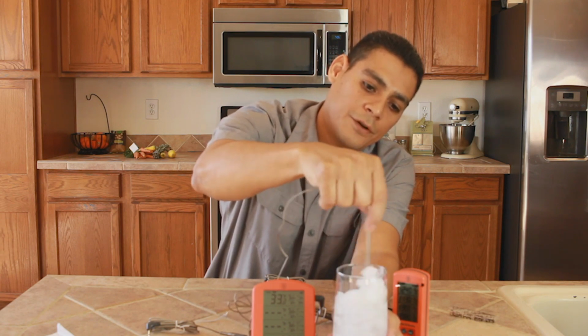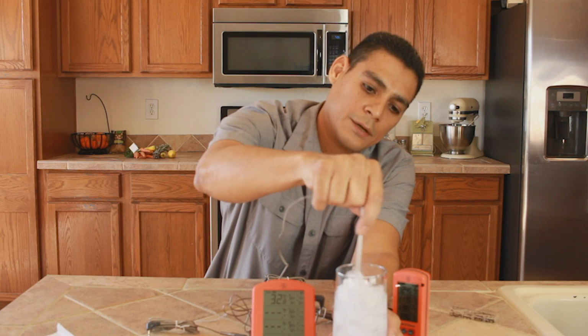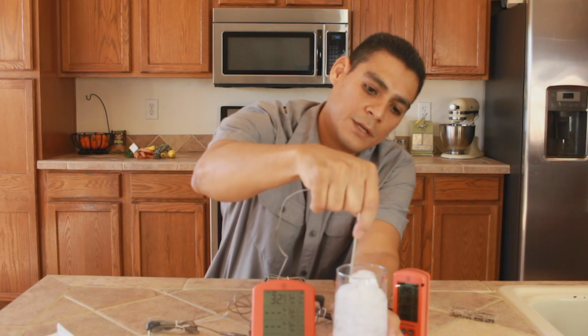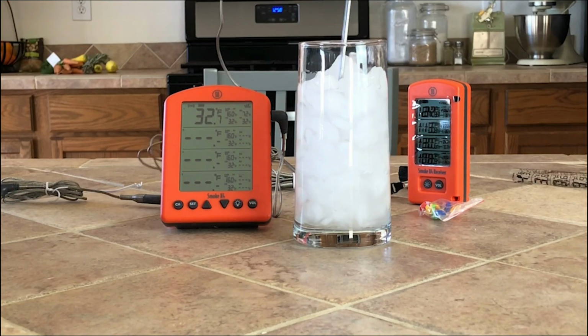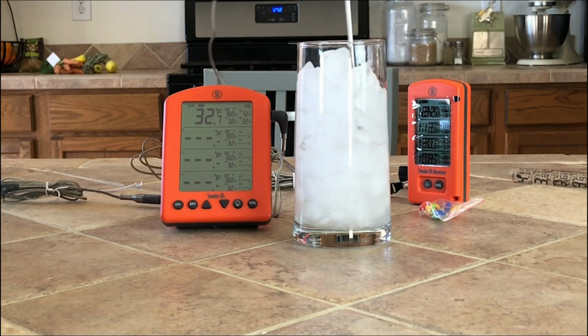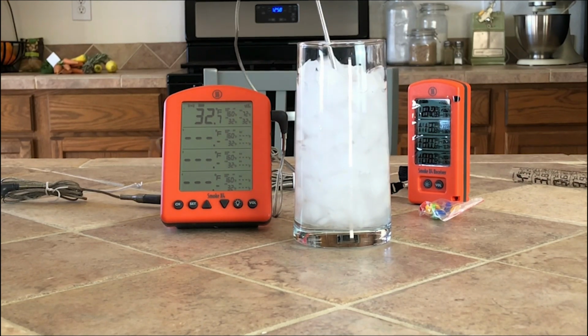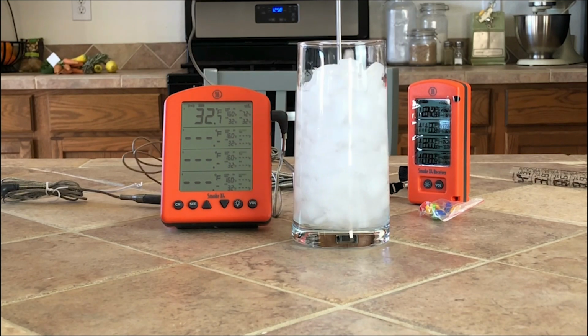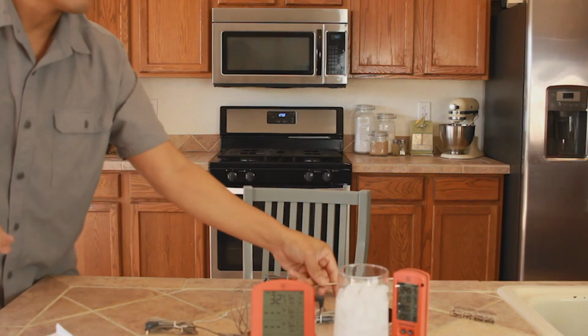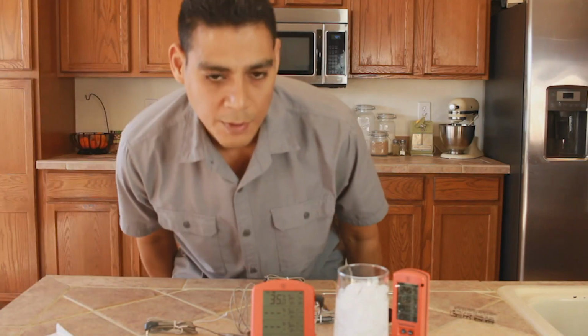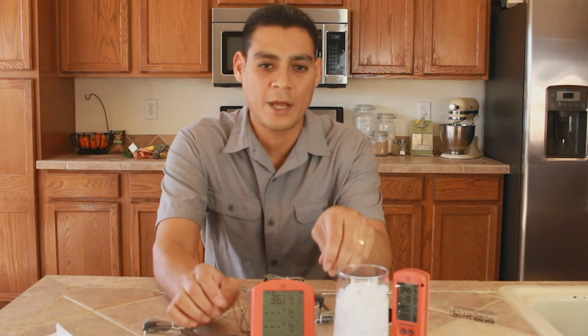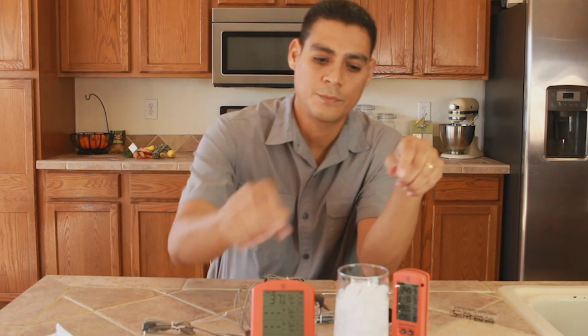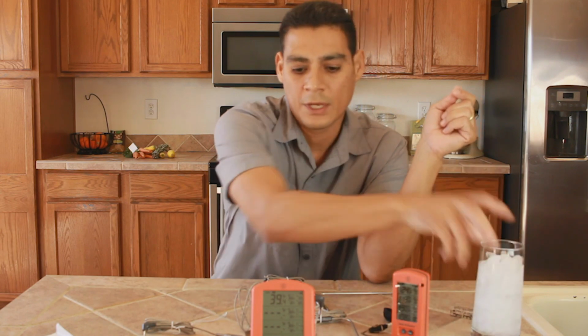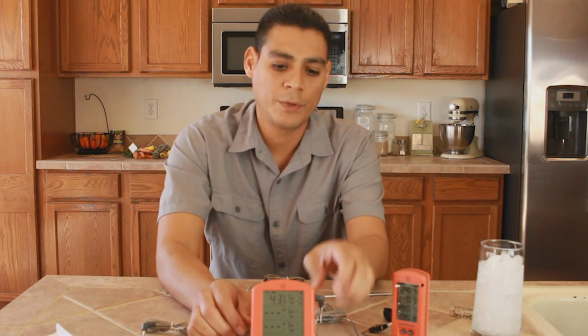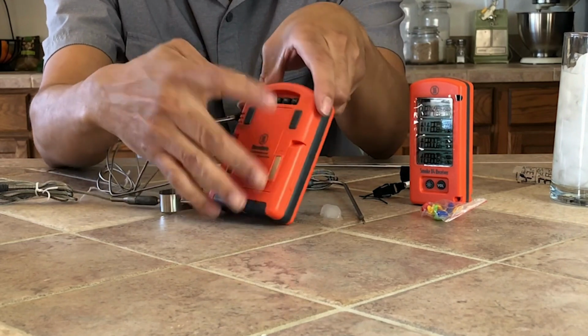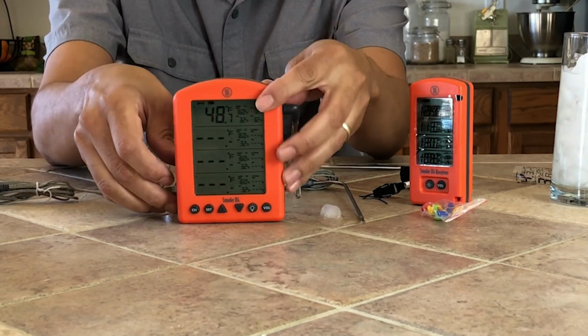We're looking for a 32-degree reading, which is basically what we want to see. As you can see, we're at 32.7 degrees. It's pretty instant that it reads that, especially if it's not transmitting, so that looks to be pretty accurate. If we wanted a more accurate reading, that's pretty much as close as you're going to get with any thermometer, but we could calibrate it. It has that option right here on the back to start doing that calibration.